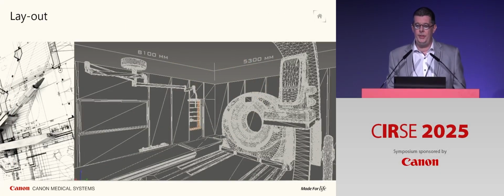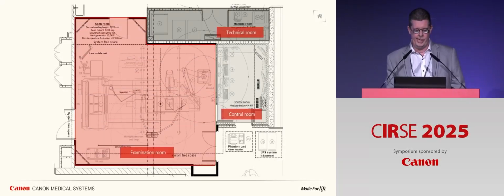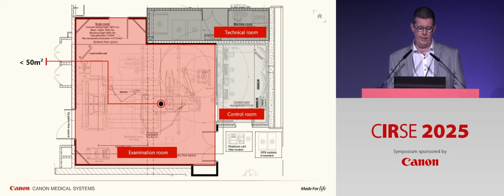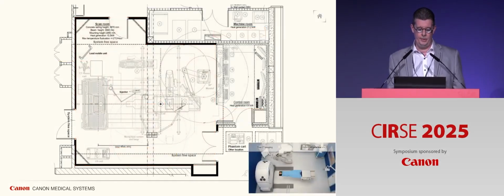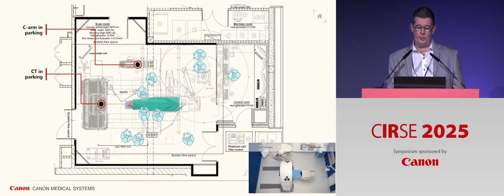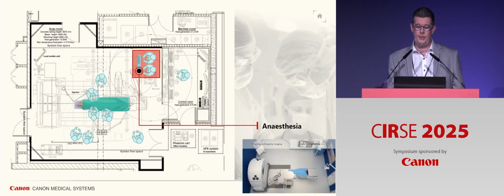Now, some words about the installation in Montpellier. We have a relatively compact room. As you can see, the examination room is a little bit less than 50 square meters. We also have the technical and the control room here. Building on our experience with the prior 4DCT system, everything was simulated in advance, not only the parking positions, but also the full range of movements of the table, the CT, and the C-arm. We also modeled the workflow of the medical staff, radiographers, anesthesiologists, as well as the ceiling-mounted equipment, such as the large display or protective shields.